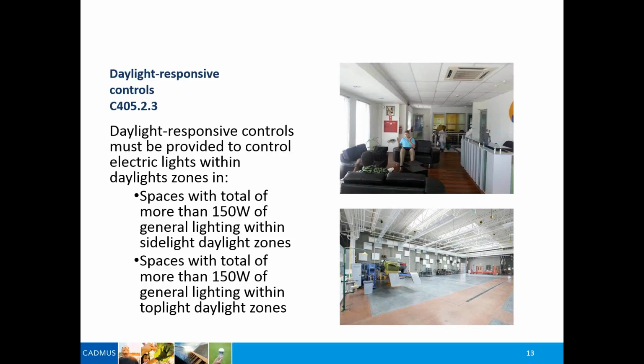This type of requirement has been in California's Title 24 Energy Code for years. It's just finally made its way into the International Energy Conservation Code. So again, from the surface of the window back 15 feet, and then 2 feet on each side of that window. Now, if you have a floor-to-ceiling height partition that is less than 15 feet from that window, then the daylight zone stops at that partition, because obviously there's no natural daylight that's going to get to the other side of it. So it can get a little complicated how you define your daylight zone, but the nice thing is the IECC has several diagrams showing how you define your daylight zone for your particular space. So from a sidelight or vertical glass standpoint, that's how you define it.